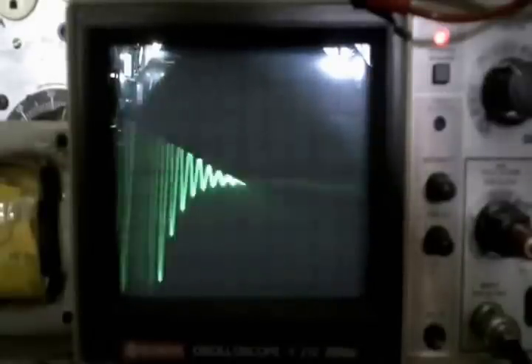In this video I'm going to demonstrate the value of a ring tester for checking shorts within a coil and some of the advantages that it has over using a conventional ohmmeter.